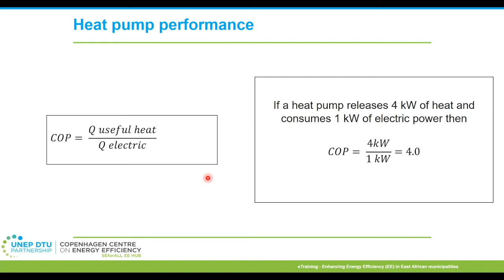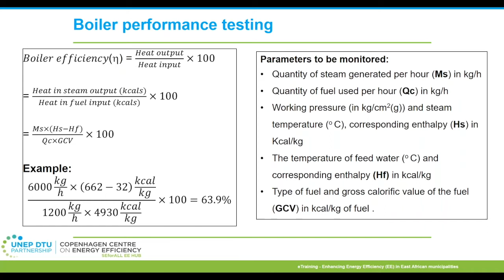For boilers, the output mentioned here is generally the numerator. It is mentioned here for steam, but you can also calculate for hot water. This calculation is nothing but output heat by input heat, which represents a direct method of calculation. There is another, indirect method which is more accurate, but it involves a bit of stoichiometric analysis also. I would not be getting into the details of that, but I can always direct you where it can be read and used.